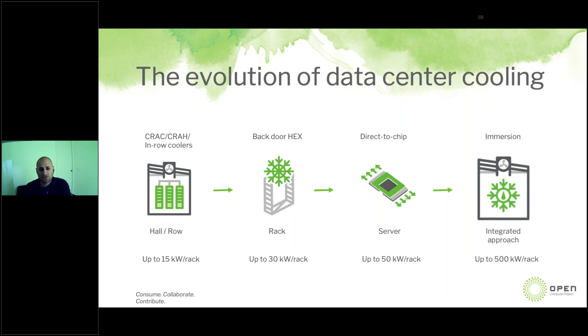There are three kinds of immersion cooling. The first is single phase: the coolant is always in liquid phase, it does not change phases. Heated coolant is circulated by pumps or by natural convection, and through a heat exchanger transfers heat to the water loop. Many generic low-cost coolants are globally available.